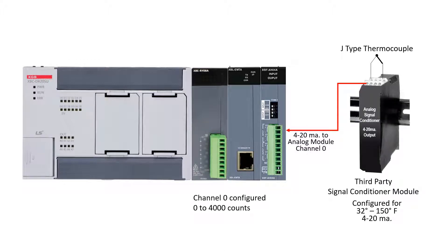Analog channel 0 has been configured in the XG5000 programming software for 0 to 4000 counts representing 32 to 150 degrees Fahrenheit.